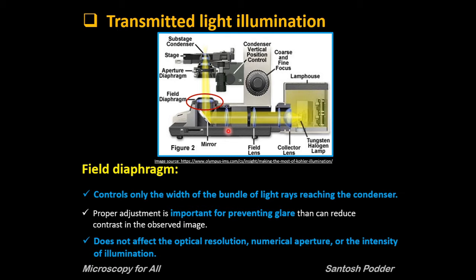There are many misconceptions regarding the function of the field diaphragm. Remember, the field diaphragm does not affect optical resolution, numerical aperture, or the intensity of the illumination. In my next video I will be talking about optical resolution and numerical aperture.